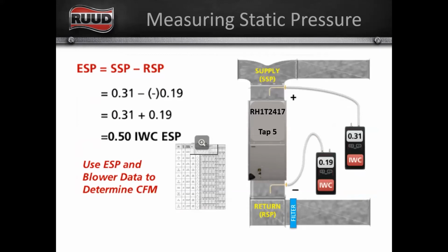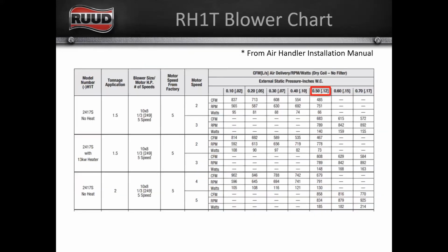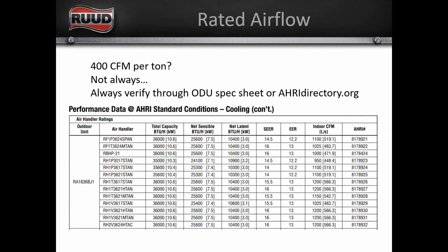So this is the same example other than the fact that we know we're using tap 5, right? So we've got a 1/2 inch water column. We're wired in, operating on tap 5, 1/2 inch, tap 5, 2417 S with a 2 ton application. We are moving 858 CFM. Okay, so we've got 1/2 inch static. We're moving 858 CFM. We're on tap 5, moving 858. Are we good to go?